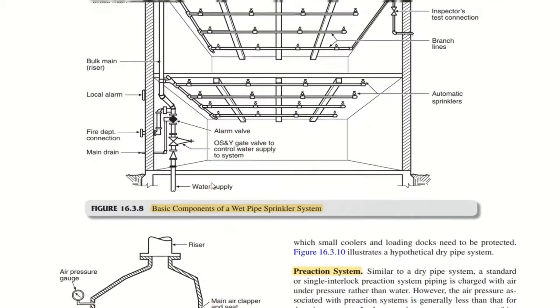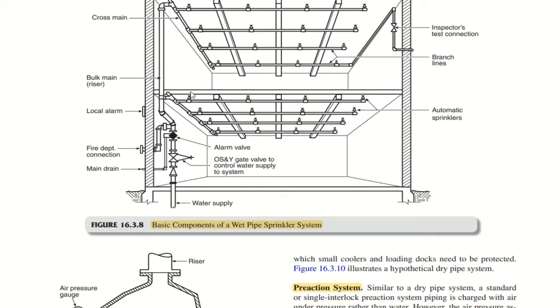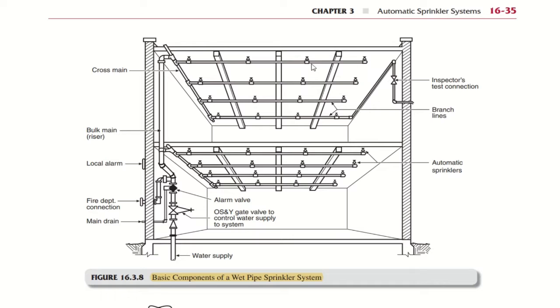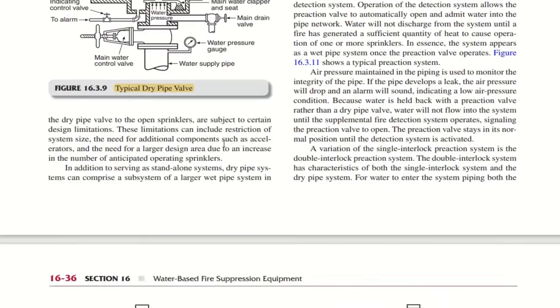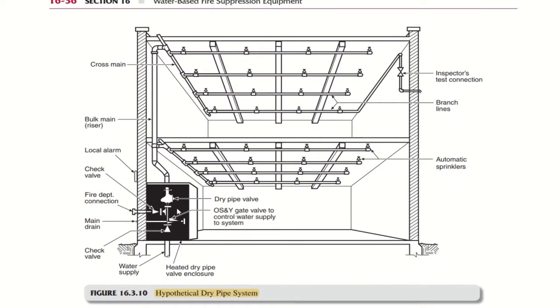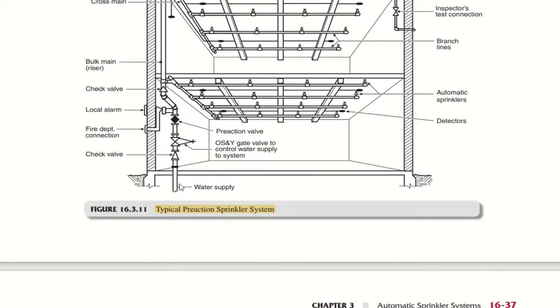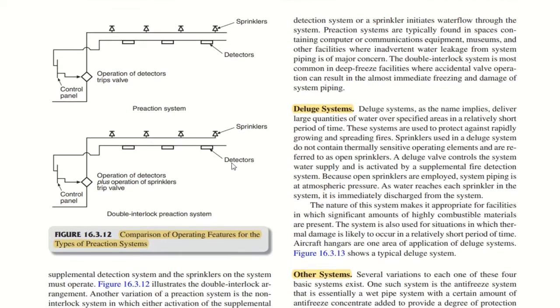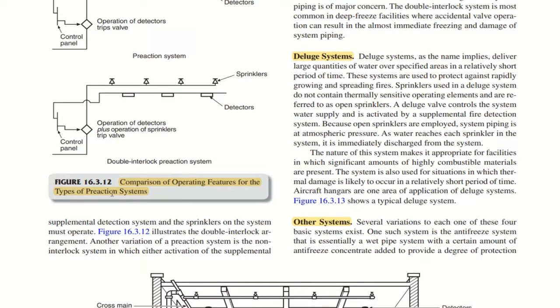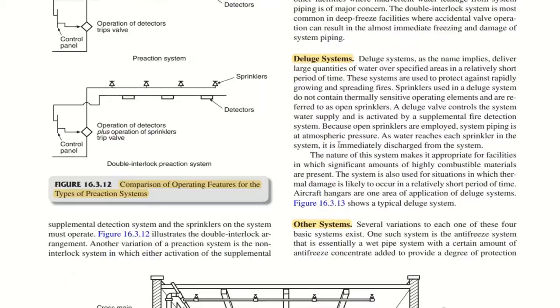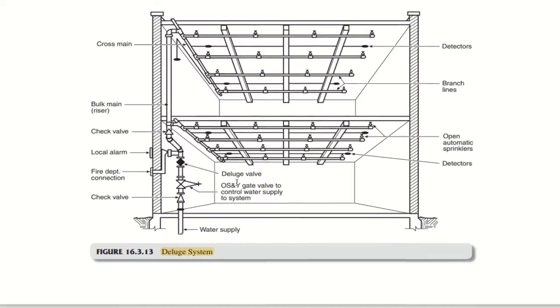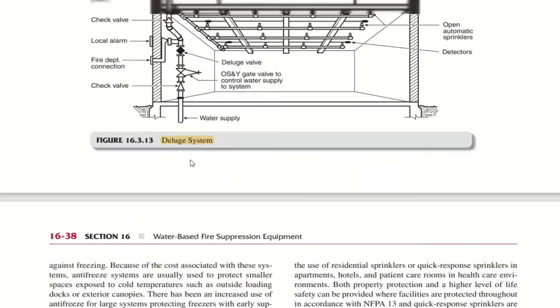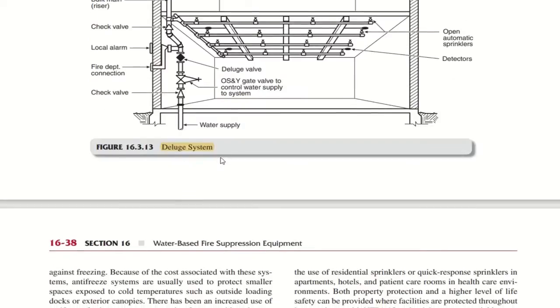In a wet pipe system you have the water supply and water is filled in the piping. Once the fire occurs, the sprinkler bulb bursts, and the water flows through the sprinklers. In a dry type, these pipes will be dry, and water will be available only up to the dry pipe valve. So here you have a typical pre-action system. Apart from that, a comparison of operating features for types of pre-action system. Here you have the deluge system, and other systems. In the deluge system you have the deluge valve here. This is also similar to the dry pipe system.